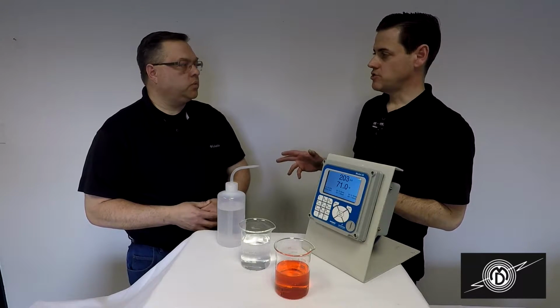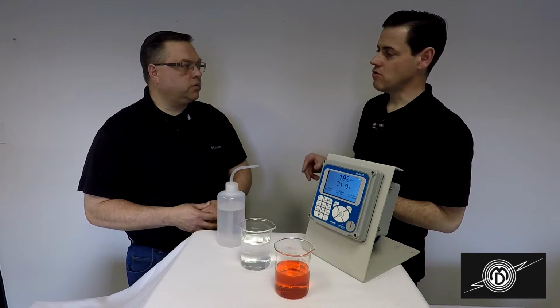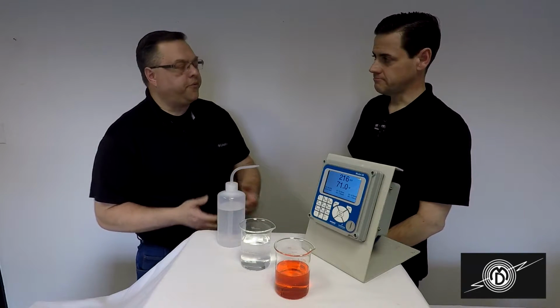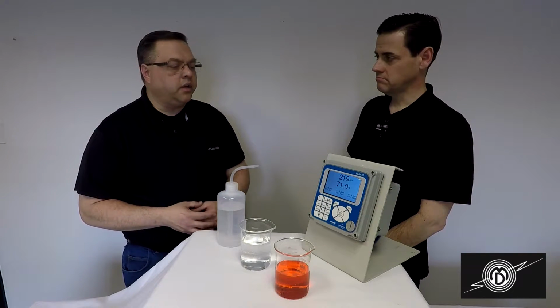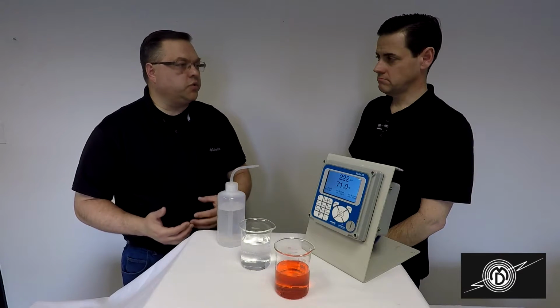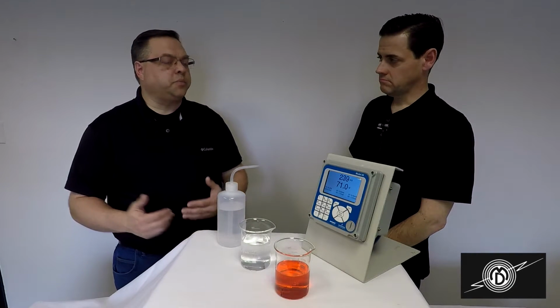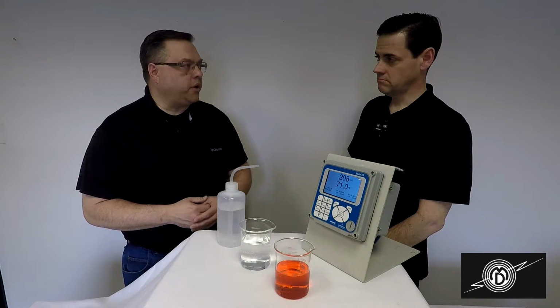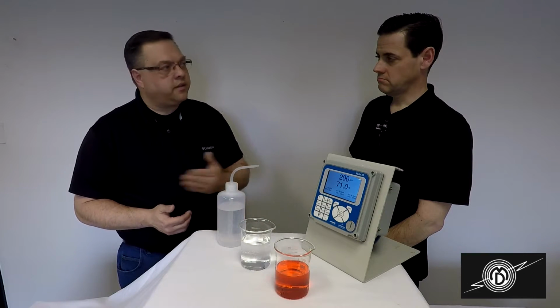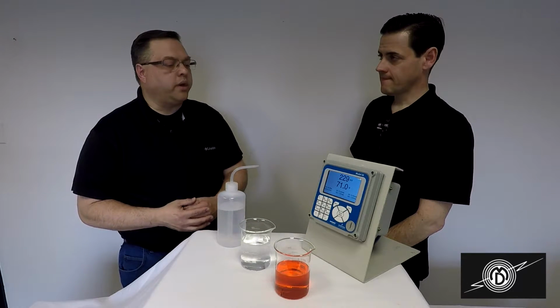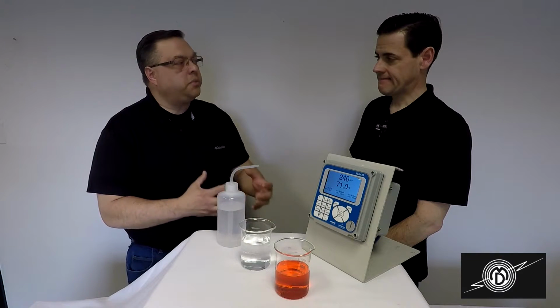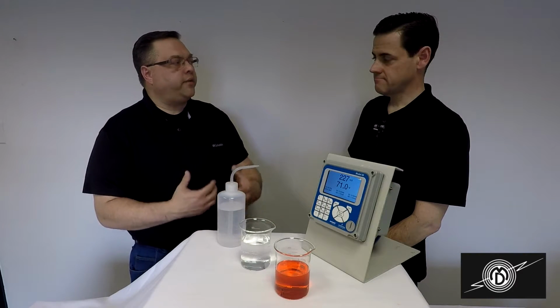Should I choose a manual standardization or automatic standardization? We prefer to use a manual standardization. As probes tend to be used and wear out, they tend to respond slower. Automatic calibrations are software sequences that time out after a certain point. With manual calibrations, you can be a little more patient and wait for the sensor to adjust to the standard.